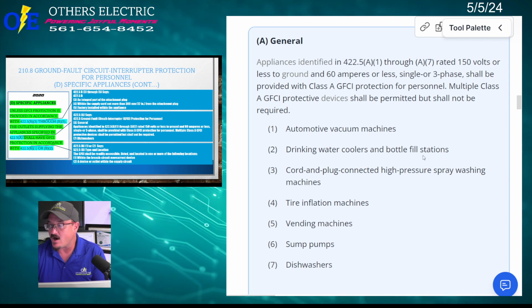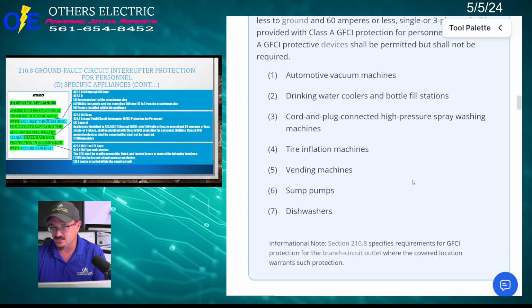Drinking water coolers and bottle fill stations, more common in residential, so that might come into contact. Cord and plug connected high pressure spray washing machines, not residential. Tire inflation machines, not residential. Vending machines, not residential. Sump pumps could be residential. No, we don't do a lot of them in Florida because we don't really have basements. But sump pumps and dishwashers, those are the two main ones that you see in everyday residential installations. So they changed 210.8D and they just redid the verbiage to add all these pieces of equipment. It used to say dishwashers. Now they put this code reference in here.